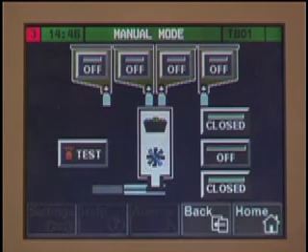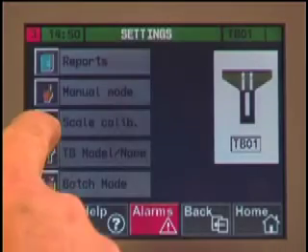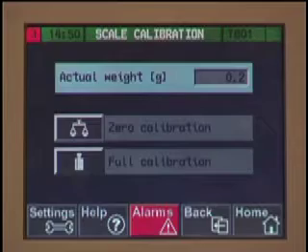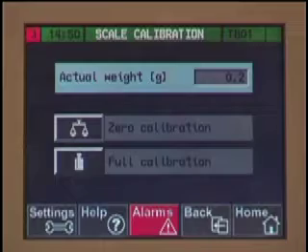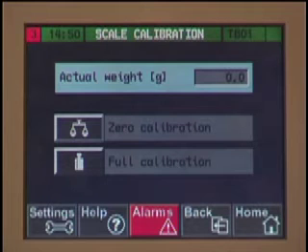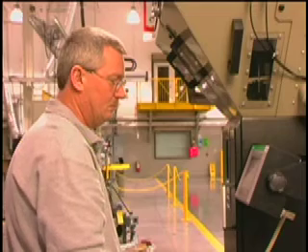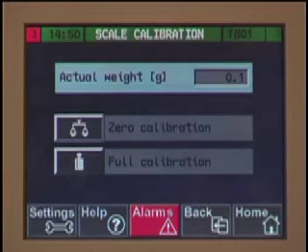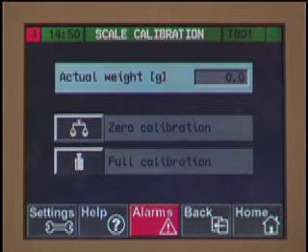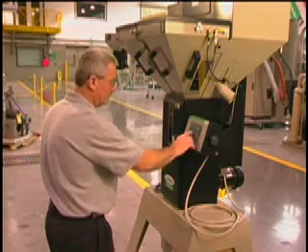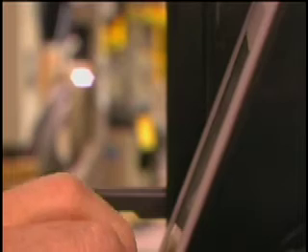Once you have viewed the manual mode screen, you can go to the scale calibration screen, which allows you to calibrate the load cells. Load cells are full-weight calibrated at the factory during shipment and/or installation — minor deviations may occur. You may need to perform a zero calibration to set the scale at zero. A full calibration is only required after a fault, the replacement of load cells, or for scale certification. Remember, a calibration weight is required to do a full calibration — consult your manual for further details.